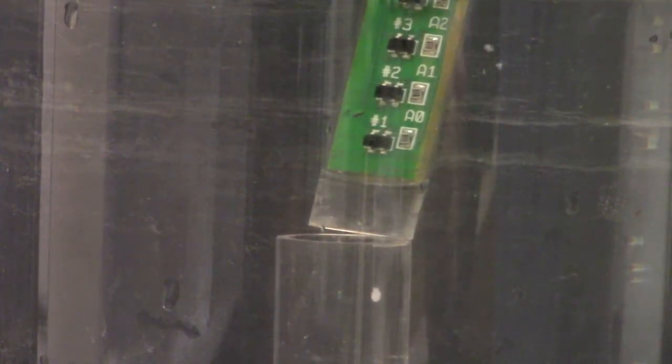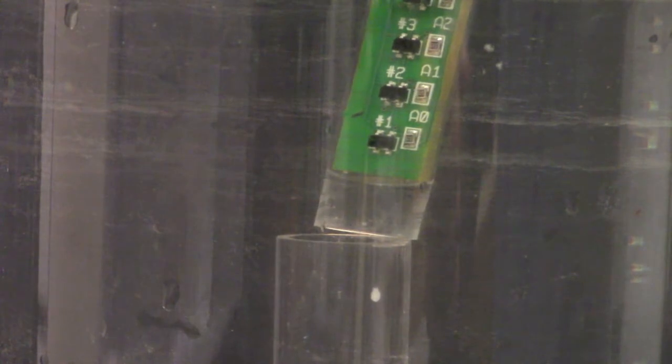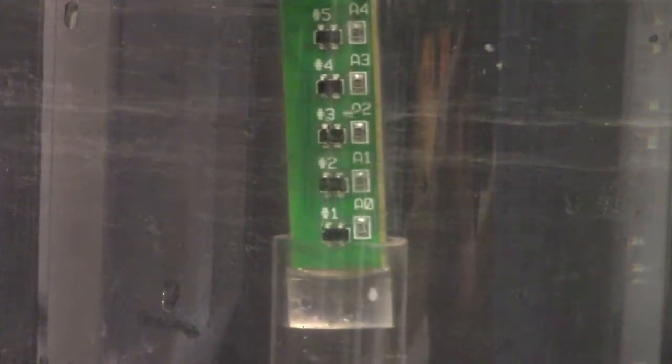These are calibrated in water and Formazine at 4000 NTU outside of the holder tube. But when using the sedimeter, it is typically placed inside this transparent holder tube.